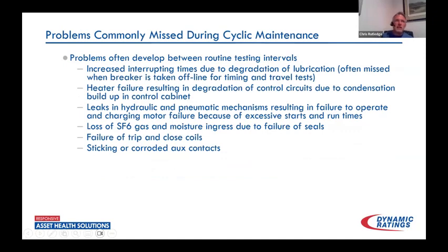The big thing about testing is you just can't do it often enough. One of the more important things you can do with circuit breakers is a maintenance trip of that breaker. If you can't get out and test it every year or every two years, at least get it operating. That's where we're really going to run into our problems — just letting them sit in a static state for a long time. However, even with the best testing and maintenance cycles, there are a lot of small problems that can occur between testing intervals that end up being big problems, which if detected sooner really wouldn't have been much of an issue.